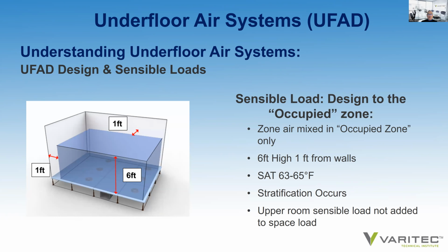Sensible load calculations need to be considered. In a UFAD system, in a thermally stratified environment, and I've covered this before, you only design to the occupied zone, which is defined, as I mentioned earlier, at 6 feet high off the floor and 1 foot off the walls. The upper 1/3 level of the room, or higher if you have 14-foot ceilings, that sensible load would not be included in the BTU sensible calculation of the occupied zone. Now that load would have to be considered at the cooling coil of the air handler, but for calculating your air volume rates to the occupant zone, they would not necessarily be included.